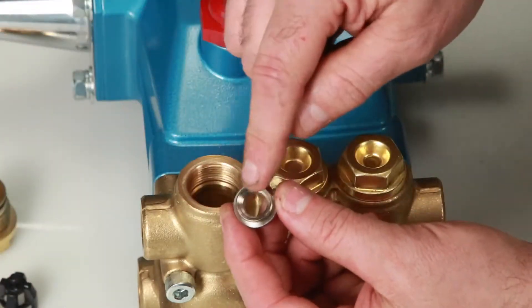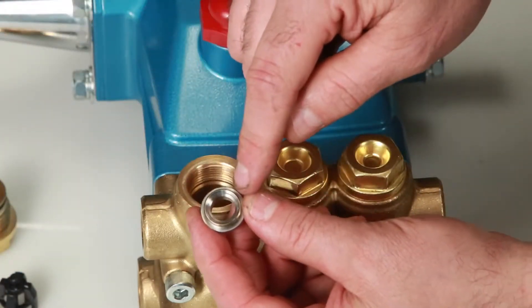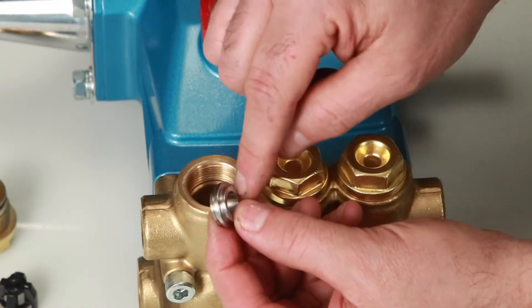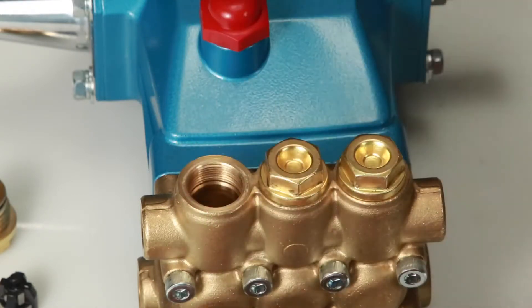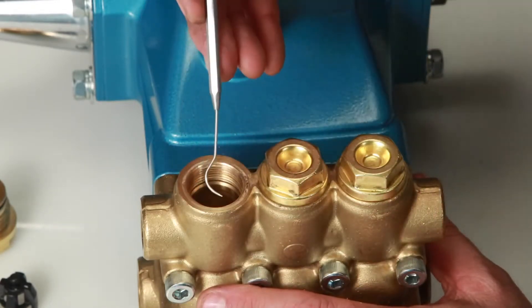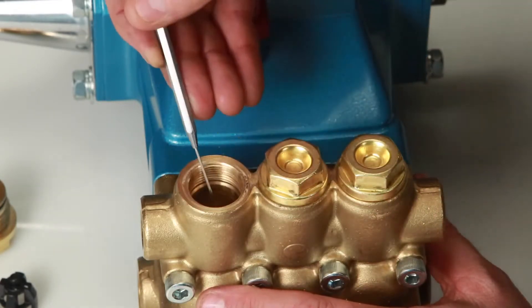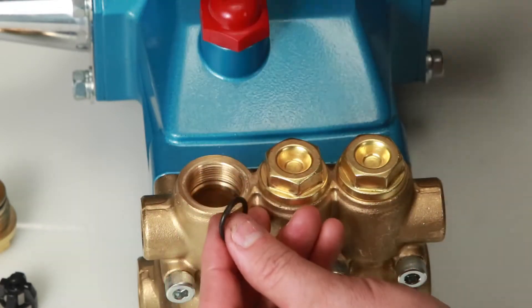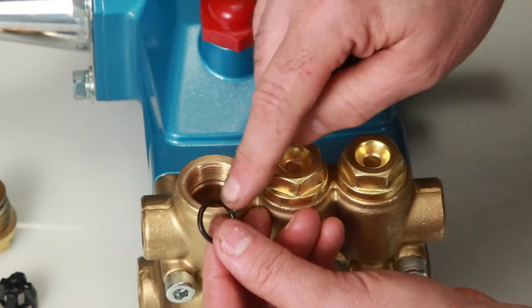Inspect tapered surface of valve seat for wear, pitting, or damage. Pitting on the valve seat or valve is an indication of cavitation. Remove the O-ring from the manifold using a small screwdriver or pick. Inspect for cuts or nicks.